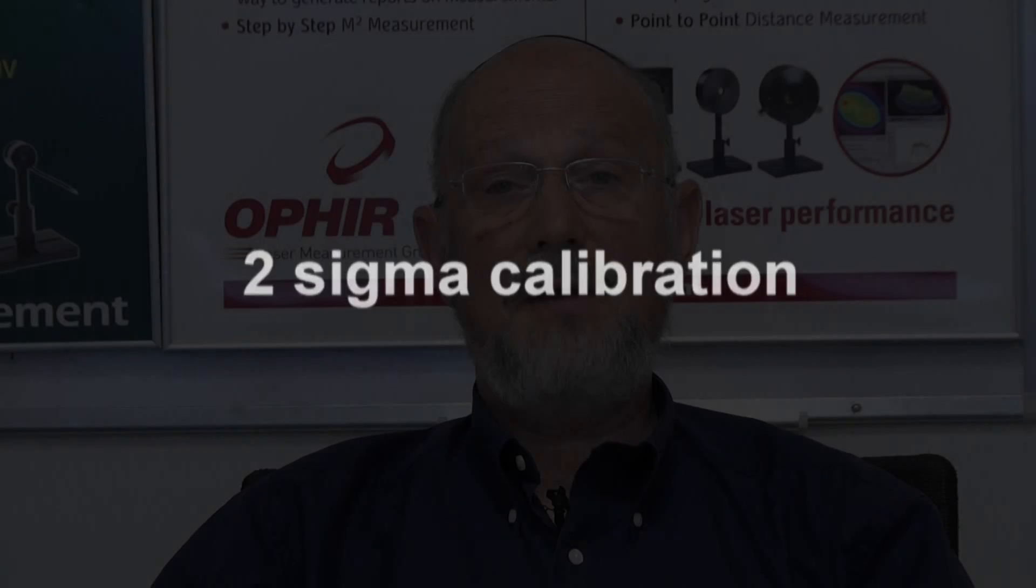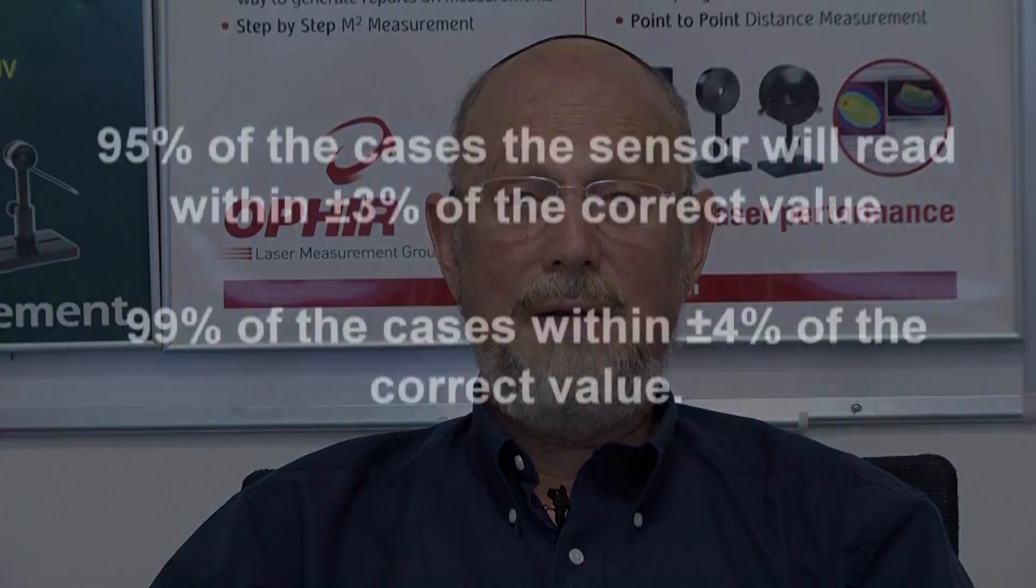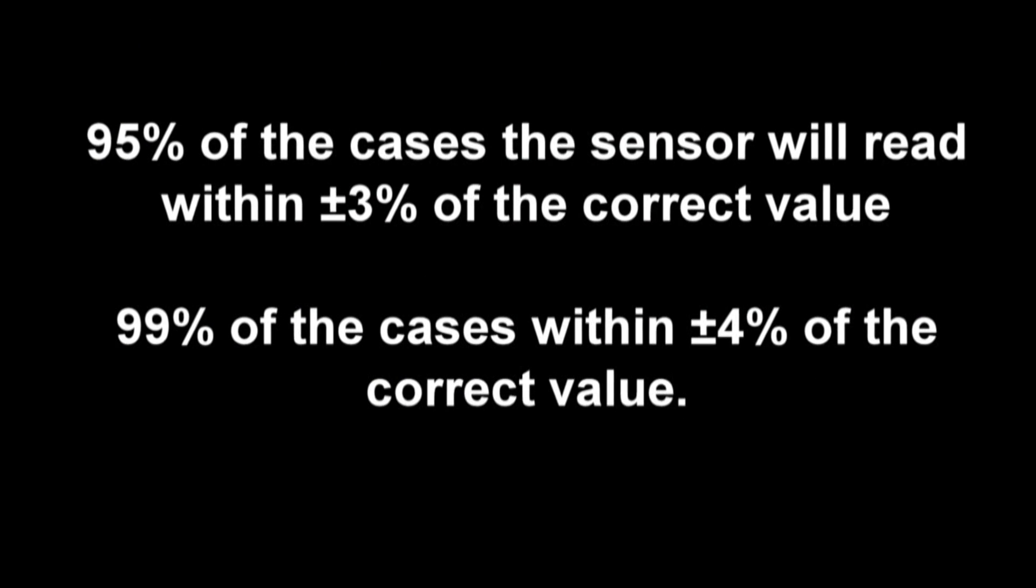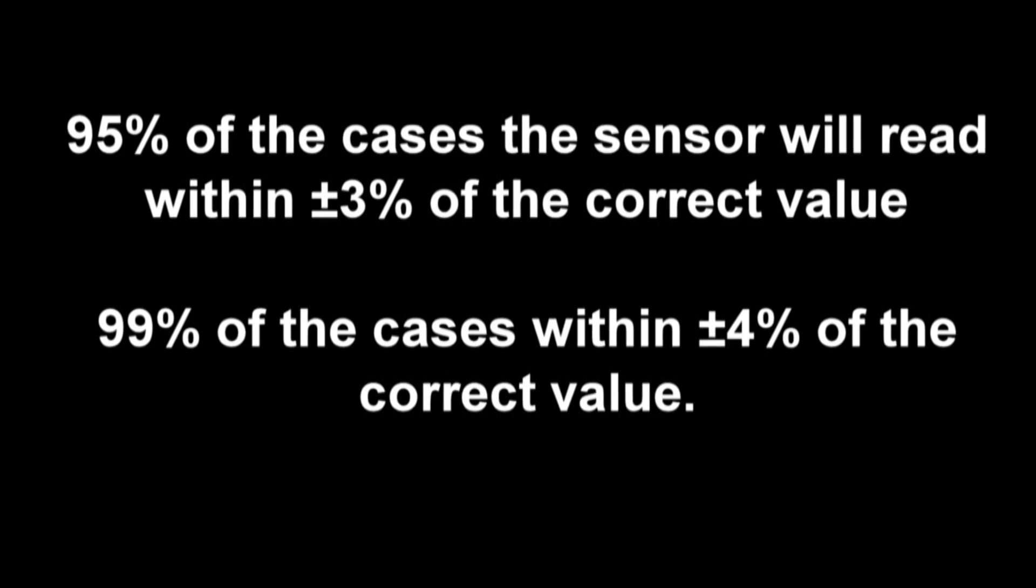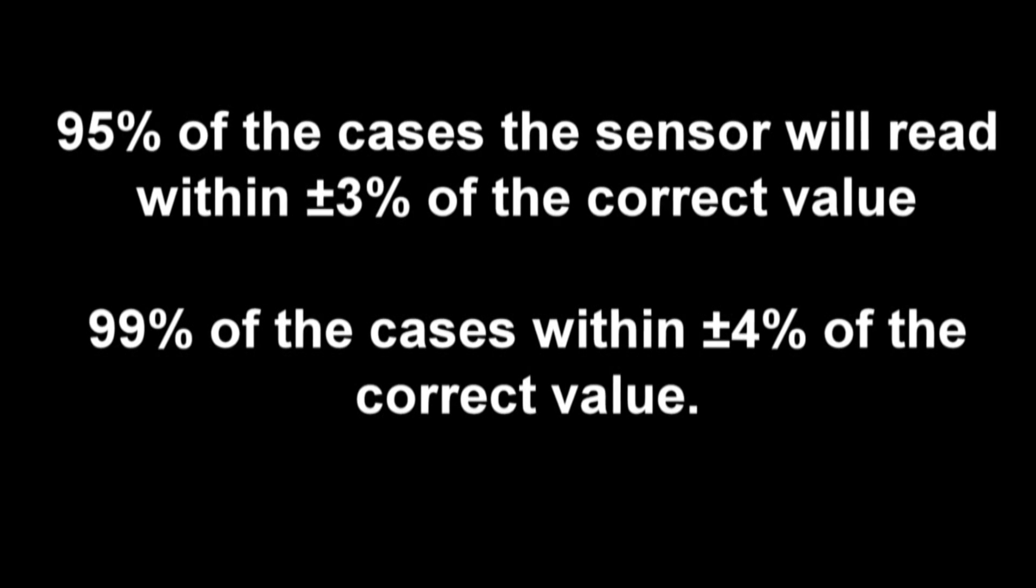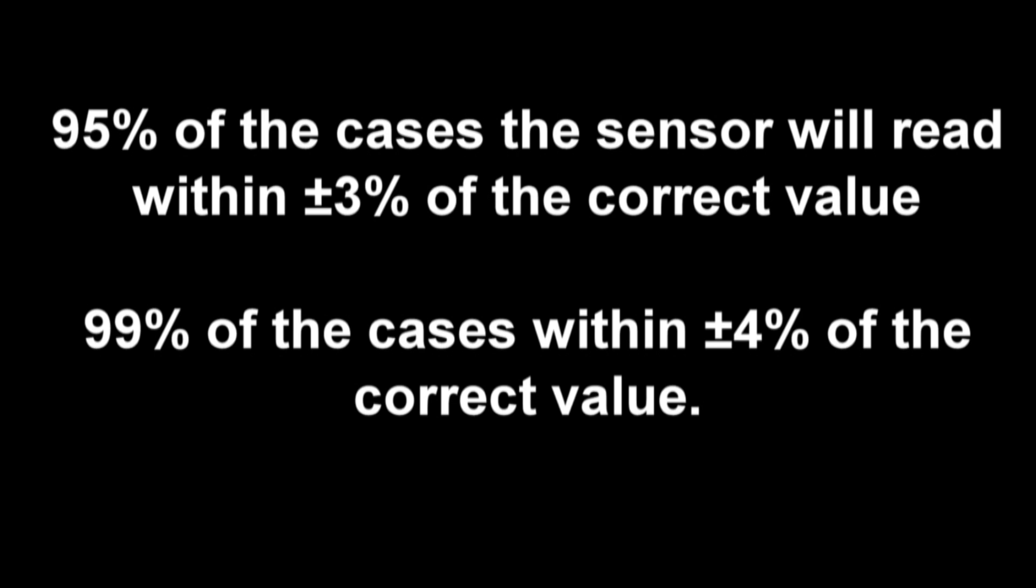When we state a calibration accuracy of plus or minus 3%, we are referring to what is statistically called two sigma calibration. This means that the errors are statistically random and therefore in 95% of the cases, the sensor will read within plus or minus 3% of the correct value and in 99% of the cases, it will read within plus or minus 4% of the correct value.